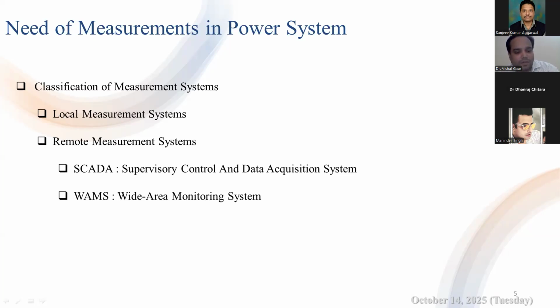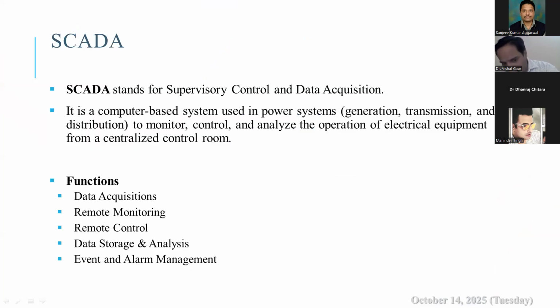So traditionally we have used SCADA for remote supervisory control. SCADA stands for Supervisory Control and Data Acquisition. It collects data every 2 to 10 seconds and is suitable for steady state operations and supervisory tasks. However, SCADA is too slow for millisecond scale dynamics and it does not provide time synchronized angles. It only provides magnitudes, that is RMS values, not angles. That is where the Wide Area Monitoring System, or WAMS, comes in.